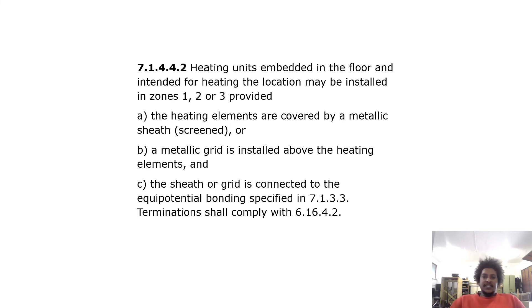Heating units embedded in the floor and intended for heating the location may be installed in zones 1, 2 and 3, provided the heating elements are covered by a metallic sheath or screened, or a metallic grid is installed above the heating elements, and the sheath or grid is connected to the equipotential bonding specified in 7.1.3.3. Termination shall comply with 6.16.4.2.